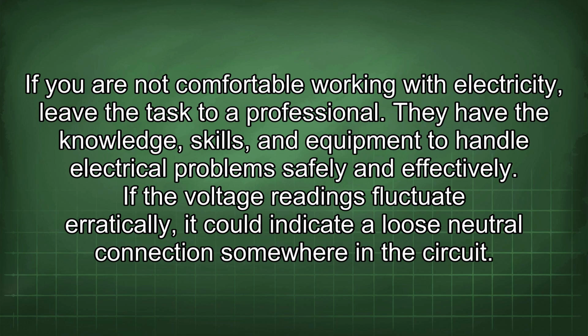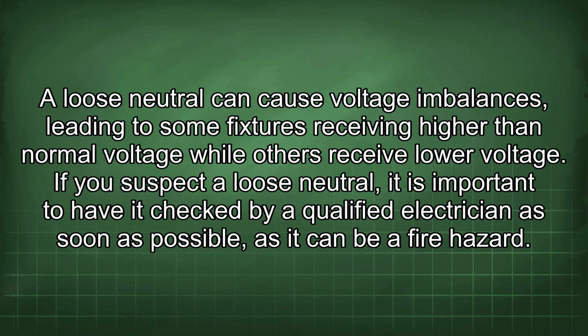If the voltage readings fluctuate erratically, it could indicate a loose neutral connection somewhere in the circuit. A loose neutral can cause voltage imbalances, leading to some fixtures receiving higher than normal voltage while others receive lower voltage. If you suspect a loose neutral, it is important to have it checked by a qualified electrician as soon as possible, as it can be a fire hazard.